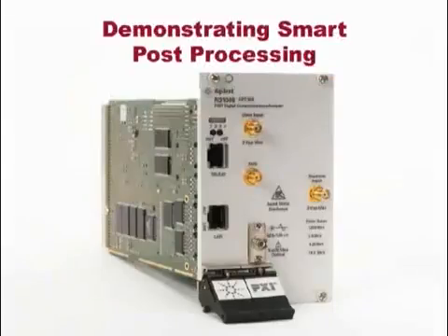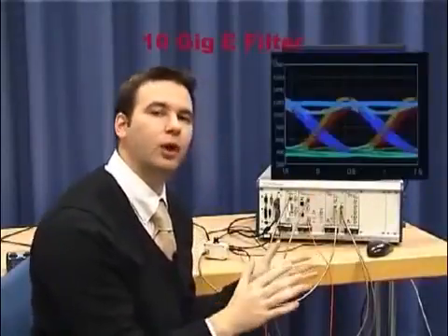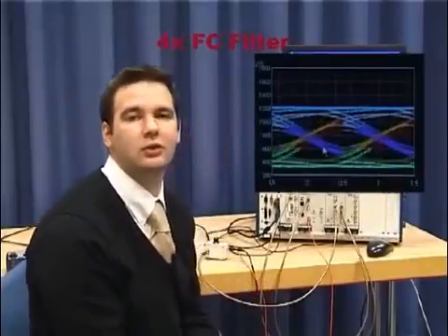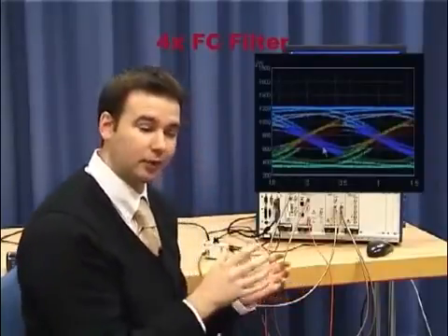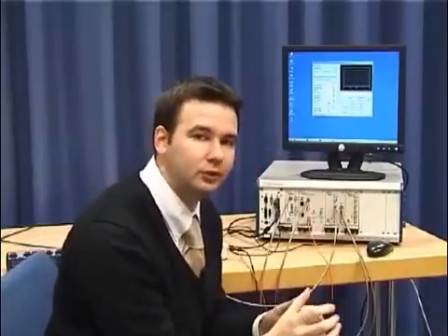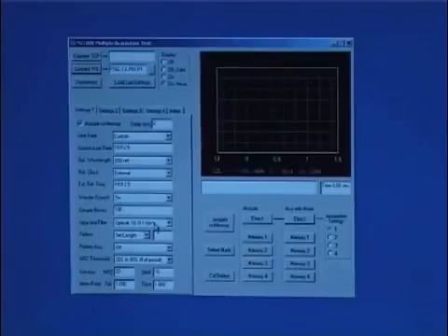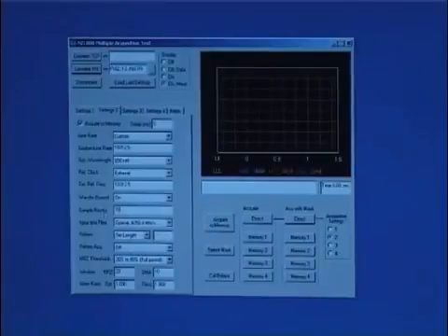So I'm going to set up two acquisitions. One: 100 waveforms with a 10-gig optical path. The second: only 16 waveforms with the 4-gig optical path. That way I'm clearly demonstrating two different acquisitions — we already know exactly how different they look. This is just proving the concept that we're able to store multiple sets of data and then process it later. Let me go to settings one, select the number of waveforms or blocks to be 100, and select a 10-gig path. For settings two, I want to select the 4-gig path and set the number of blocks to just 16.